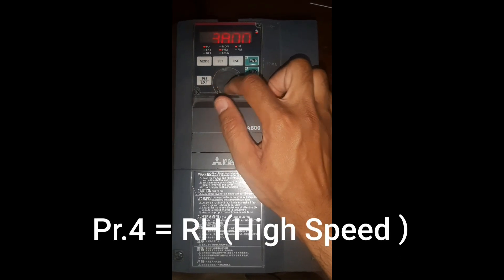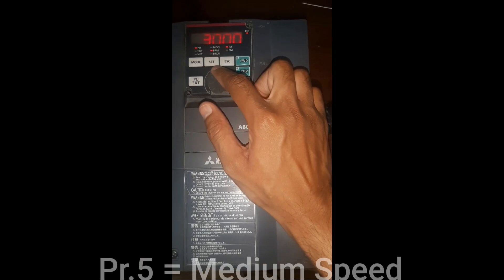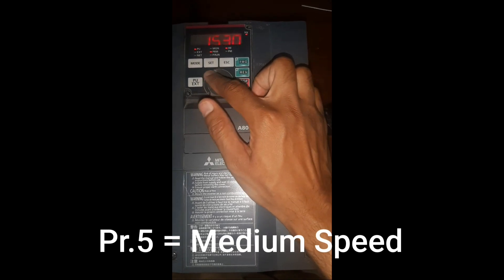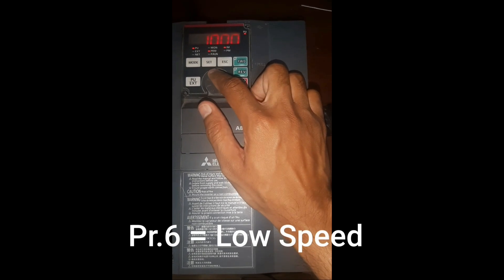The next parameter is parameter number 4, that is the high speed, also known as the 3rd step speed. I will set this parameter to 20Hz. The next parameter is parameter number 5, also known as medium speed or 2nd step speed — I will set it to 15Hz. Parameter number 6 is the 1st step speed, also known as low speed — I will set it to 10Hz.